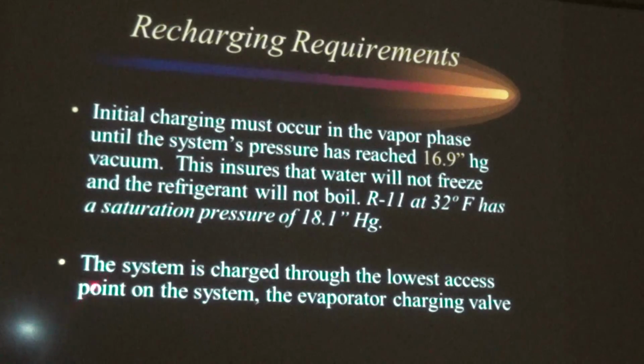The system is charged at the lowest access point on the system, the evaporator charging valve. Another key one, remember that one, because it's definitely on the test. And these are kind of counter to what you expect. You don't really think of charging into the evaporator charging valve. But you've got to remember, we're charging as a vapor, and we're trying to get the refrigerant in the vapor state up to where it's not going to boil off the refrigerant. We want that to happen once it gets into the evaporator.